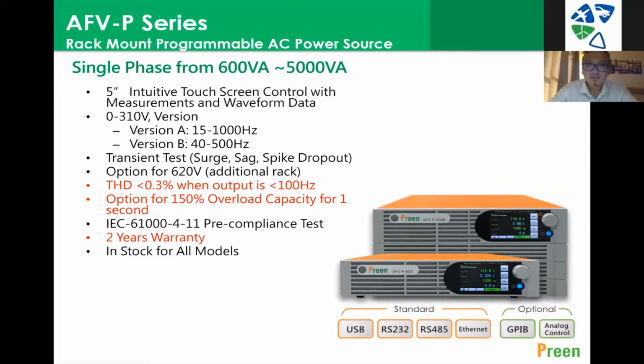So 50 hertz or 60 hertz can be used for commercial testing. If you're shipping a product to Europe, you can do 50 hertz testing, and if you're manufacturing a product for military use, you can use 400 hertz. It also supports surge, sag, and spike testing, since sometimes the standard requires transient testing.